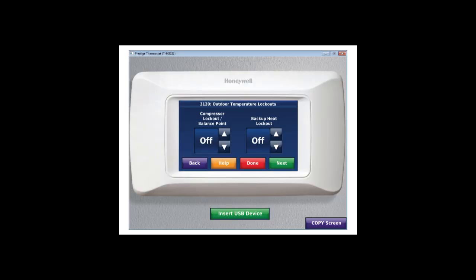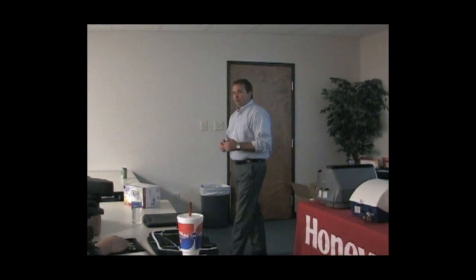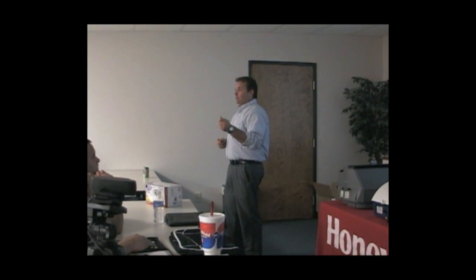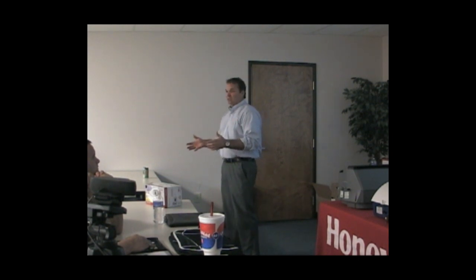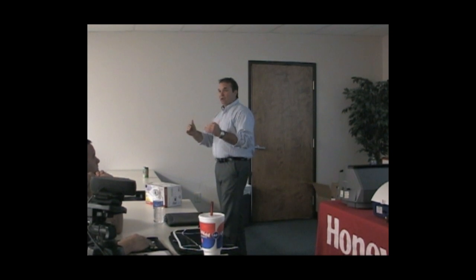And then this is where you'd set your balance point for your dual fuel. There are laws in Kentucky, and actually if you read the Indiana Energy Code that came out earlier this year, they really want you locking out the electric strips above 40 degrees if the heat pump can produce enough heat. Now the inspectors are not enforcing this. They don't know how, but it is the code.